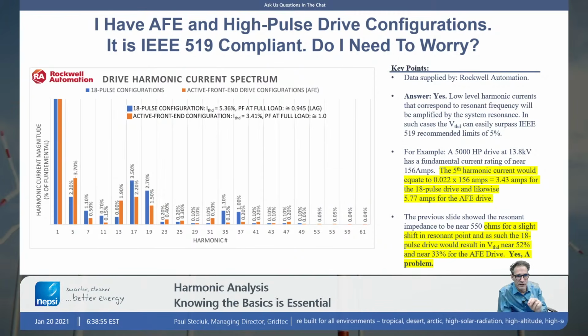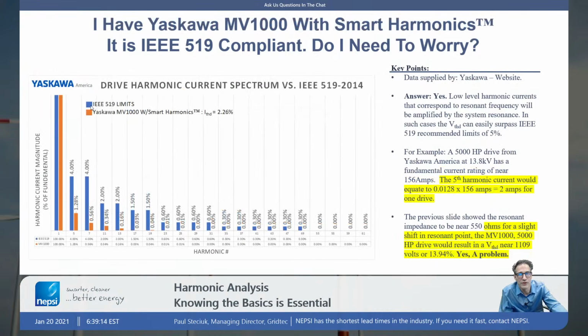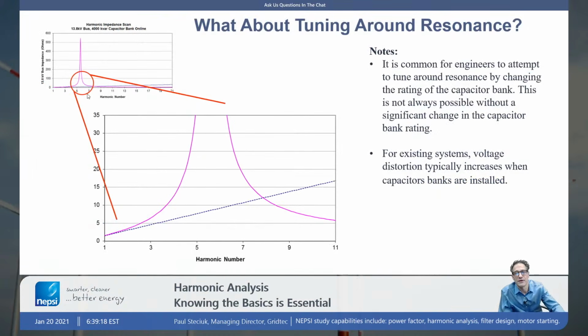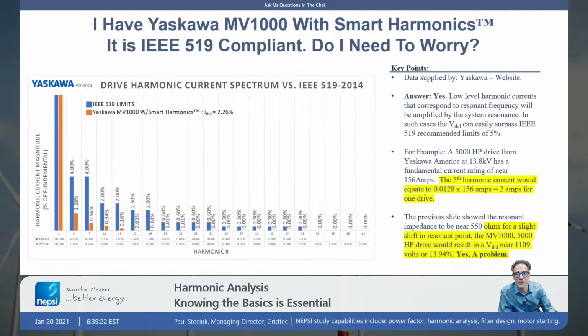So the point here is that when you're adding capacitors to the network, even with active front-end drives or high pulse drives, you still need to be concerned about harmonic resonance, because even a small value of current injection, even a small amount of distortion, can result in an amplification of that, and it can exceed your limits. You can do the same thing with Yaskawa. Doesn't matter who it is. I've also done it with Siemens. All of those drives put out very low values of distortion. They're great. It means that if you're installing a filter system in your project to avoid resonance, that filter system does not need to be as robust. It can be a smaller filter, but it doesn't remove the requirement that you need to detune your cap bank, which is another way of saying I need a harmonic filter. But you can't install standard capacitors.